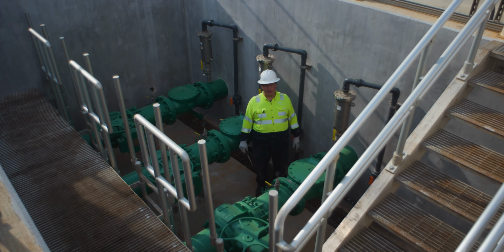Okay, we're at CP100, which is the pump control panel. This door will stay closed until you open up the main, and it does not have a dead front on it. It's got the safety and arc flash information on this door. It says 1.93 calories per centimeter squared, so a 4-foot arc flash boundary. So if you're doing hot work in here, which you shouldn't be doing, you would have to cordon off a 4-foot area so other people couldn't be around while you're doing the hot work. Of course, you have to have the appropriate PPE as well.